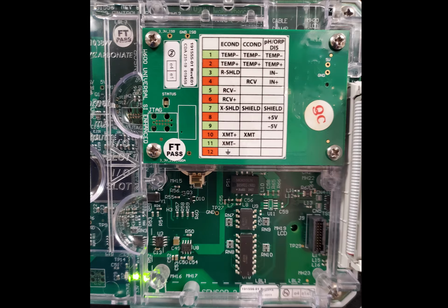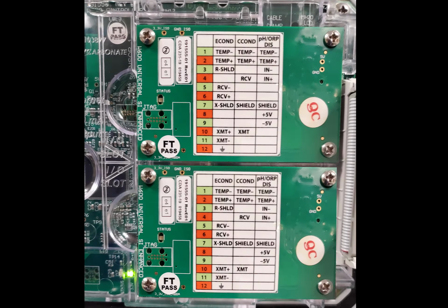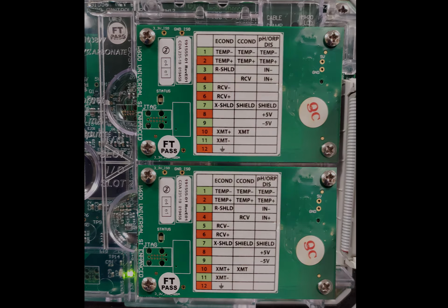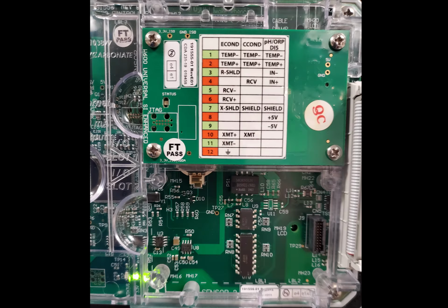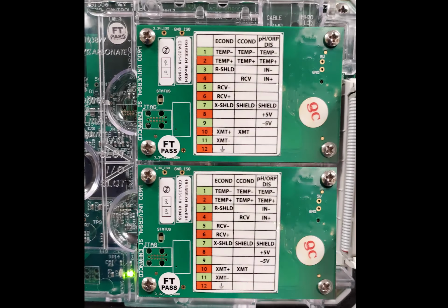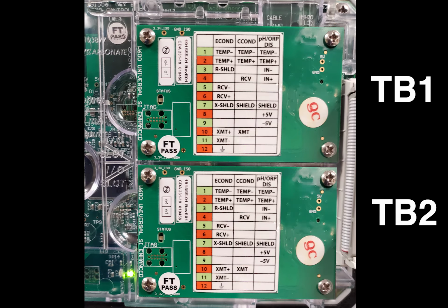There will only be one sensor input card on the controller if monitoring one boiler, and 2 sensor input cards on the controller if monitoring 2 boilers. For one boiler, the sensor input card will be installed on the top of the controller door, and for 2 boilers, one on top and one on the bottom. The top card is aligned with the sensor input S11, and the bottom card will be aligned with sensor input S13. Sensor S11 gets wired to TB1, and sensor S13 gets wired to TB2.